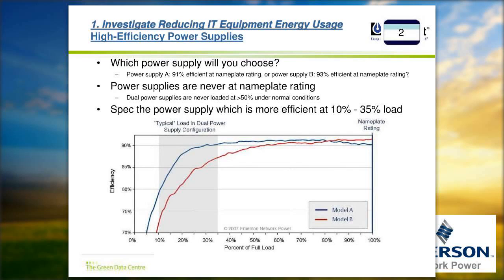The next approach for reducing IT equipment energy usage is the selection of SMPS. Most SMPSs are designed considering fully configured servers, all highly populated, where the efficiency expected is very high. Considering dual SMPS inside the box operating in load sharing mode, most SMPSs operate between 25 to 40% of the range, and you should demand energy efficiency of SMPSs at a loading factor of 15 to 35%. That's how you can select the most energy efficient server SMPS, which will again help reduce energy consumption at the IT side itself.